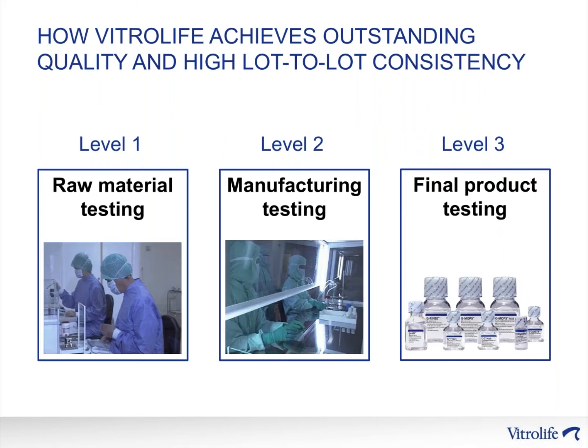At Vitrolife, we perform quality control on mainly 3 different levels during manufacturing. Level 1, raw material testing. Level 2, testing during manufacturing, also referred to as in-process testing. And level 3, final product testing. We place particular emphasis on raw material testing, such as medium components and contact materials. Testing of raw materials gives us a unique possibility to actually create high quality, since we can test a lot of different raw materials and then select the one with the best quality and use that in our production.